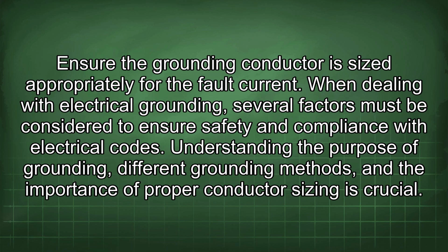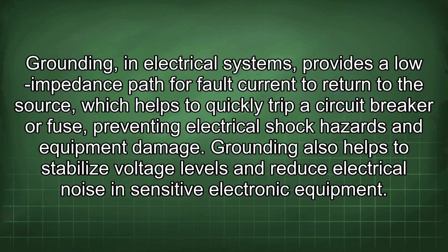When dealing with electrical grounding, several factors must be considered to ensure safety and compliance with electrical codes. Understanding the purpose of grounding, different grounding methods, and the importance of proper conductor sizing is crucial. Grounding in electrical systems provides a low impedance path for fault current to return to the source, which helps to quickly trip a circuit breaker or fuse, preventing electrical shock hazards and equipment damage. Grounding also helps to stabilize voltage levels and reduce electrical noise in sensitive electronic equipment.